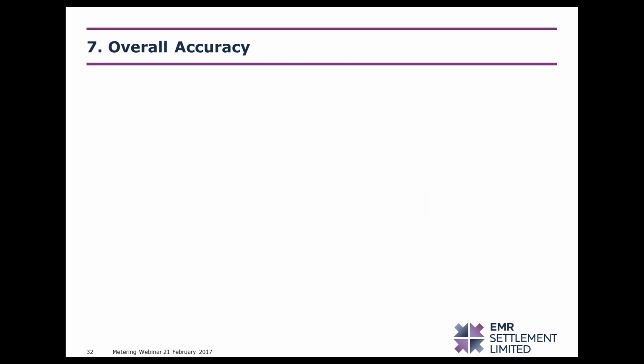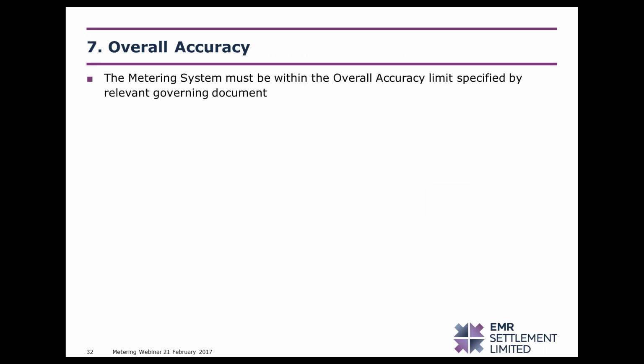Lastly, looking at overall accuracy. Bespoke metering and settlement metering specifies that the entire metering system must be within limits of overall accuracy. This limit is specified in the relevant governing documents. So for settlement metering, this is the codes of practice, and for bespoke metering, this is the bespoke technical requirements in Schedule 7 of the rules. As I alluded to earlier, this can cause problems where you don't have evidence of the actual errors of the metering equipment. The overall accuracy will include all metering equipment, so this can be meters, current transformers, and voltage transformers.